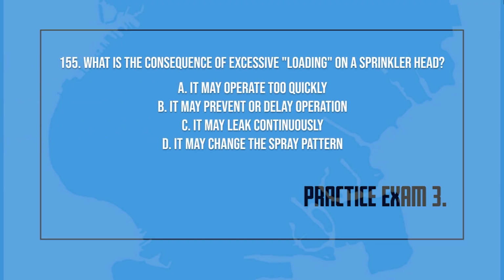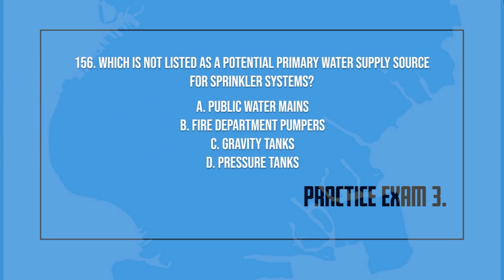(155) What is the consequence of excessive loading on a sprinkler head? A. It may operate too quickly. B. It may prevent or delay operation. C. It may leak continuously. D. It may change the spray pattern. (156) Which is not listed as a potential primary water supply source for sprinkler systems? A. Public water mains. B. Fire department pumpers. C. Gravity tanks. D. Pressure tanks.